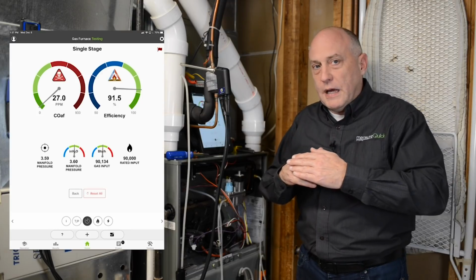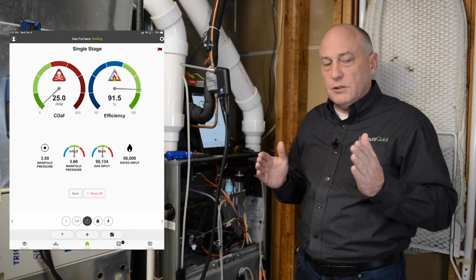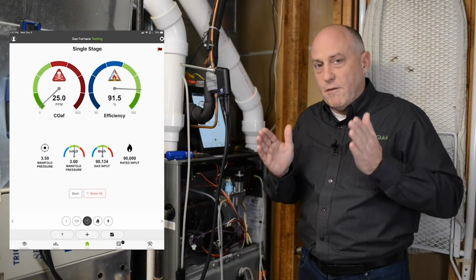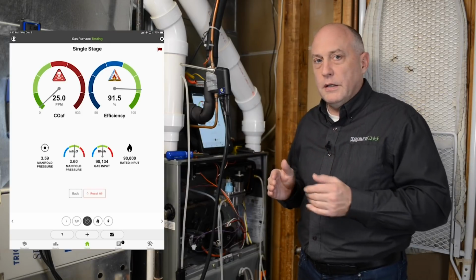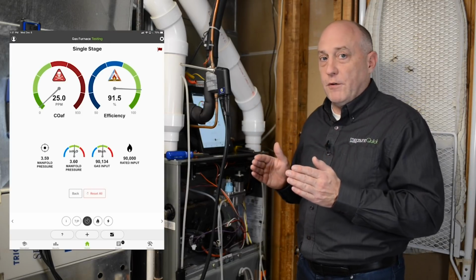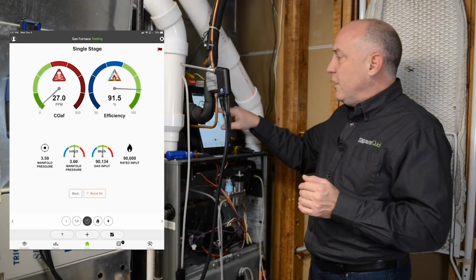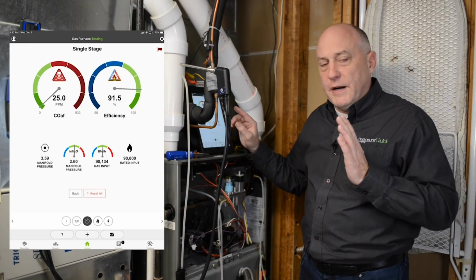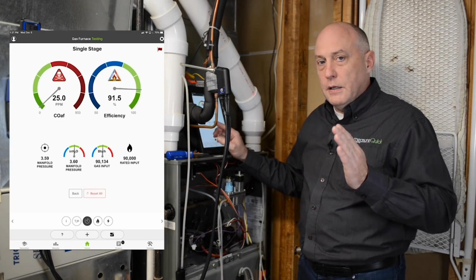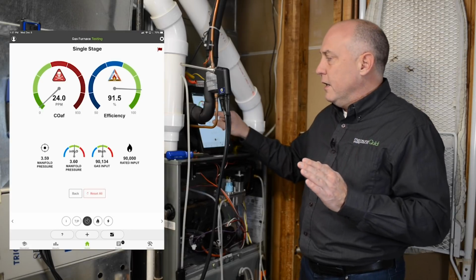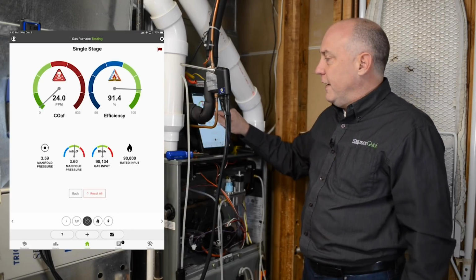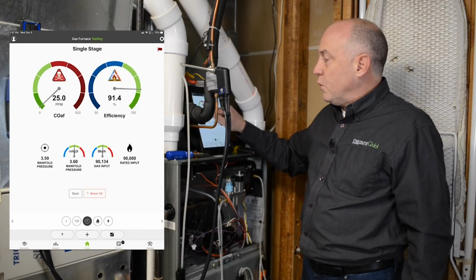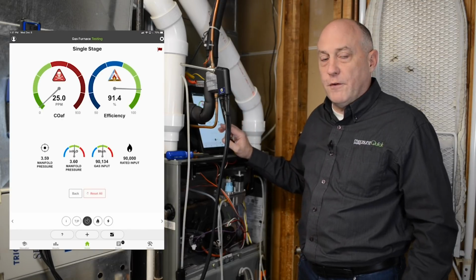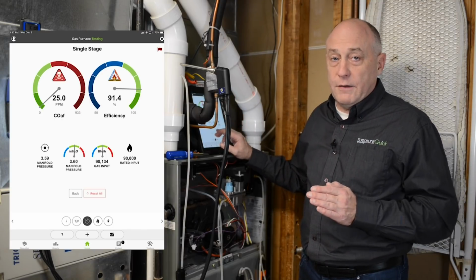So I can tell you without any doubt at all that this furnace is running the way that it should run, because I have all the targets, one after the other, laid out showing you where every reading should be for combustion analysis. Now here's the other thing we did on here. Your two primary gauges are combustion efficiency and safety. You always want to be looking at that CO air free. So you can see right now we're running about 25 parts per million CO air free, which is a very, very good reading for this furnace.